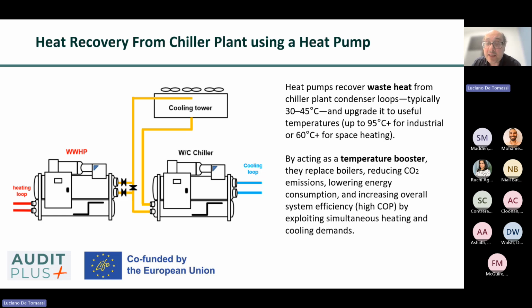The key principle is that the heat pump does not create heat from electricity alone, but instead upgrades existing waste heat, making the overall process significantly more efficient than direct electrical heating or fossil fuel boilers. In operation, the heat pump is typically connected in parallel with or integrated into the chiller condenser loop. When there is simultaneous cooling and heating demand, the system becomes particularly efficient because the chiller continues to reject heat into the condenser loop while the heat pump extracts and upgrades it.